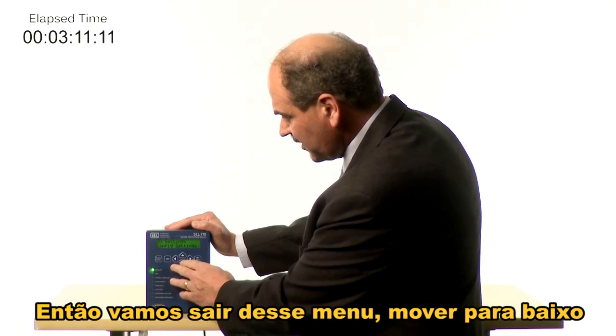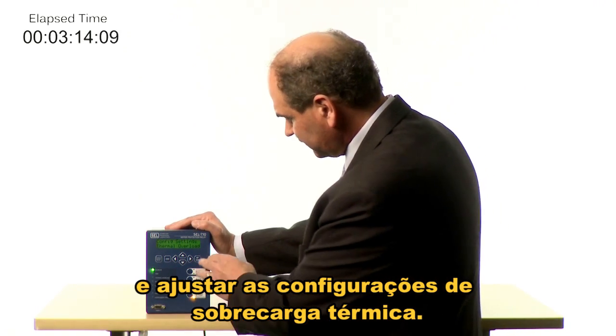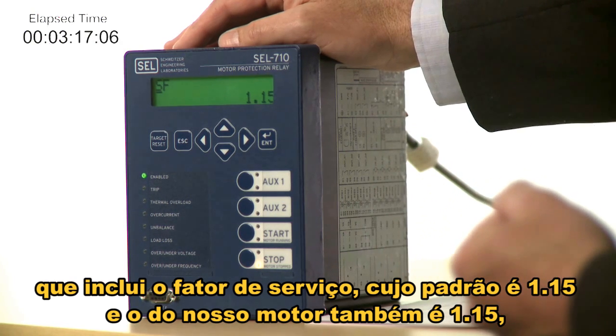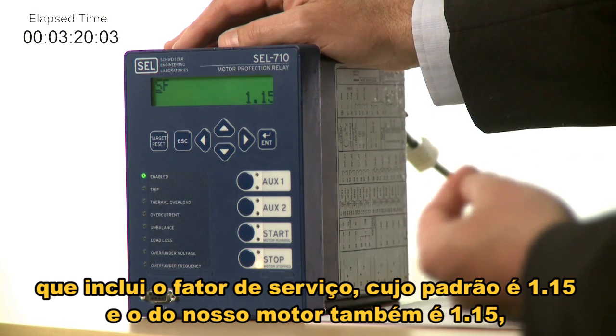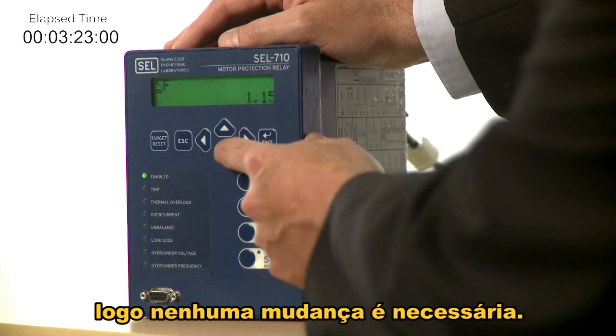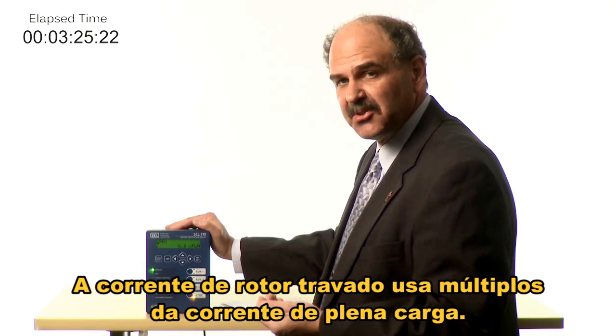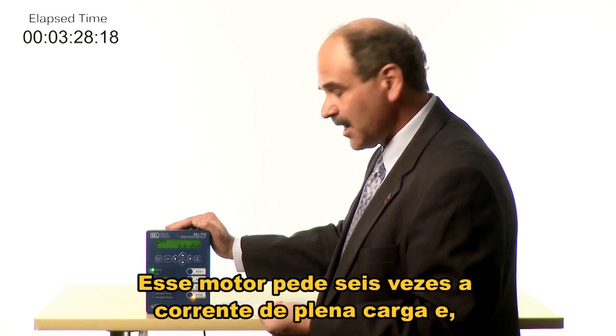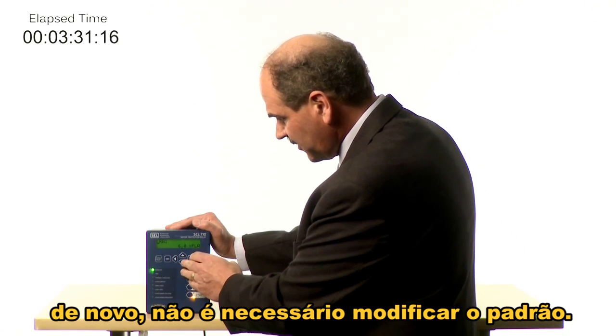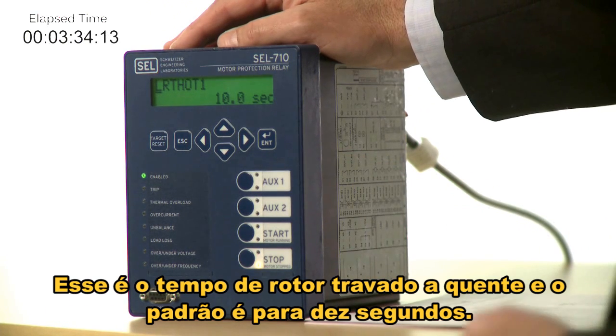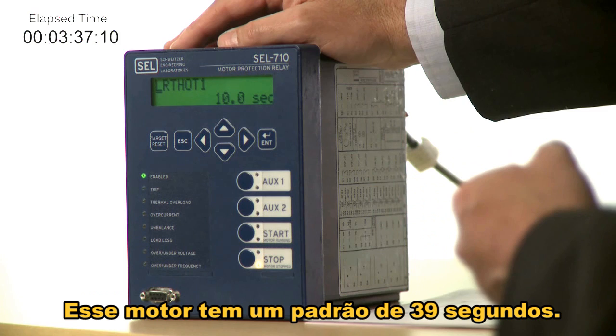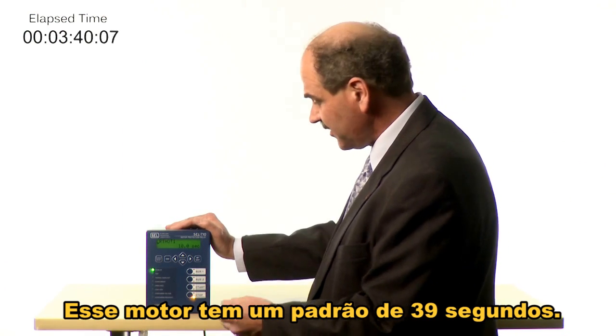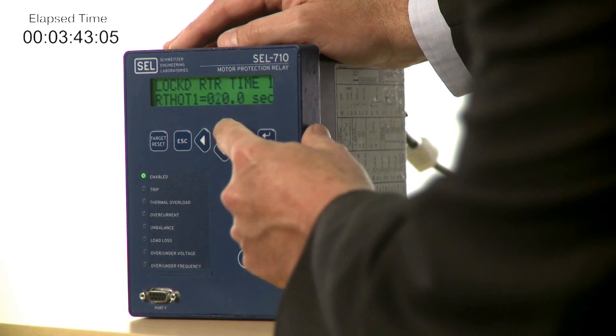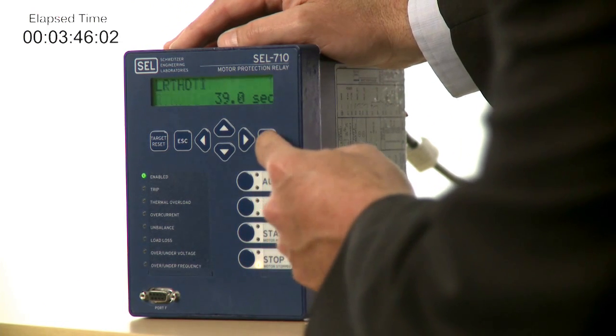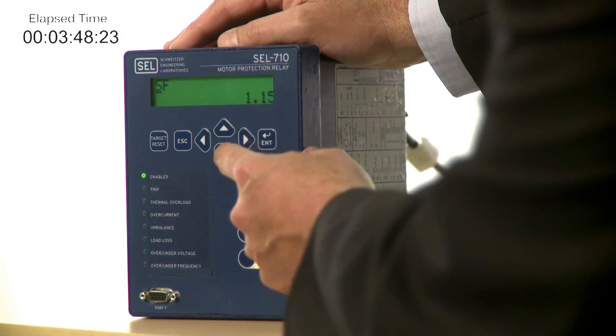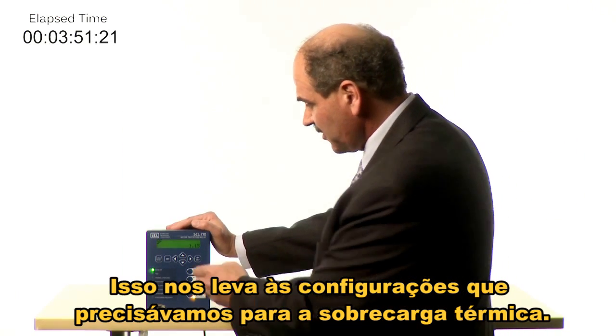So we'll move back out of this menu and move down and set the thermal overload settings, which include the service factor, which the default is 1.15, and our motor is also 1.15, so no change is necessary. The locked rotor amps uses multiples of full load amps. This motor was rated for 6 times full load amps, and again, no change is necessary from the default. This is the locked rotor hot stall time, and the default is 10 seconds. This motor has a rating of 39 seconds for that locked rotor hot stall time. And that takes us through the settings we needed for the thermal overload.